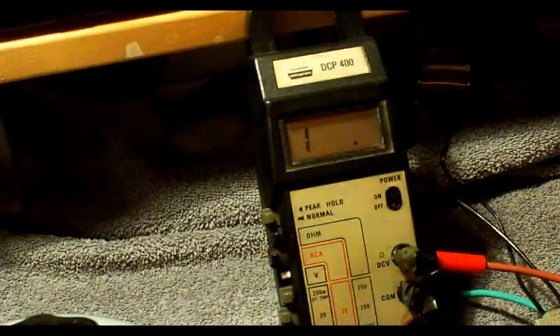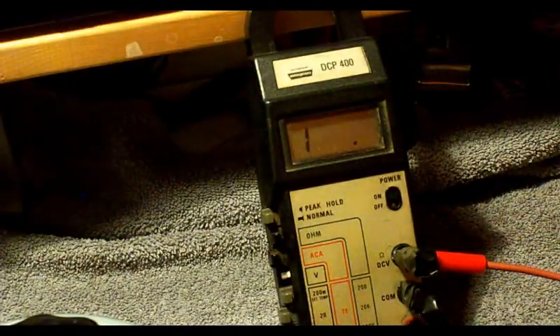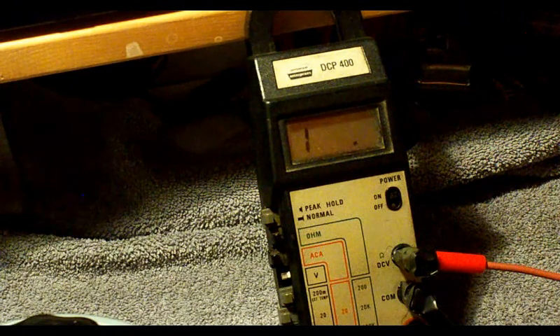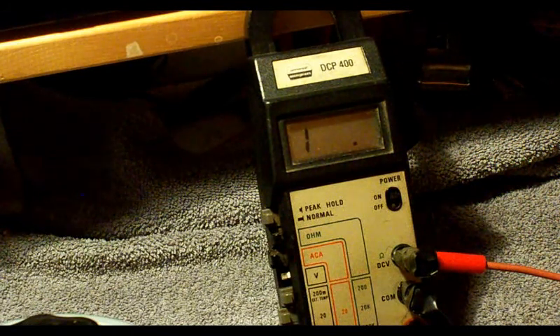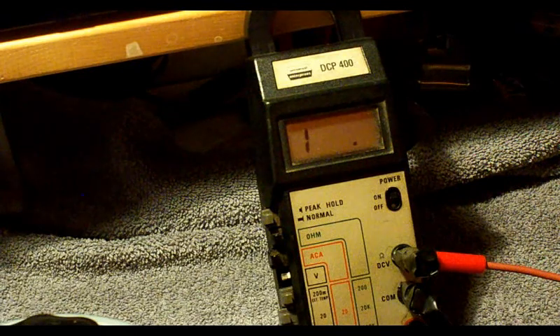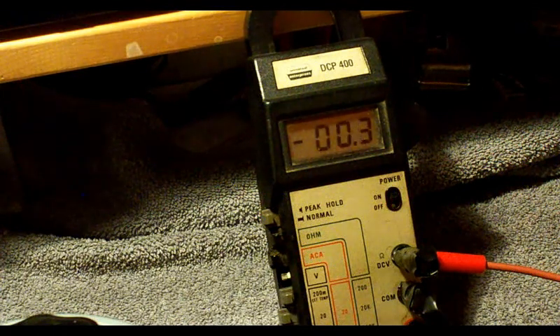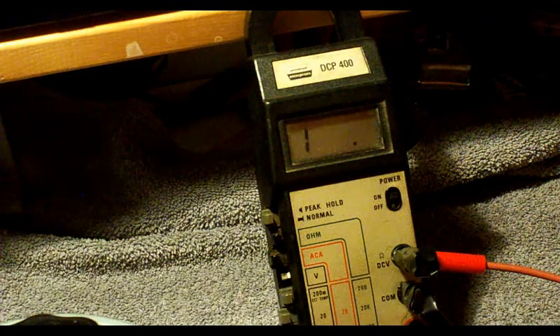And now open. So again, this transformer, let's check across the primary. And we read open. Okay. Let's check across one side of the primary to one side of the secondary. And we read a dead short, 0 ohms. 0 ohms. So an absolute dead short through this transformer. Now let's check the good one. We're going to check across the primary winding.